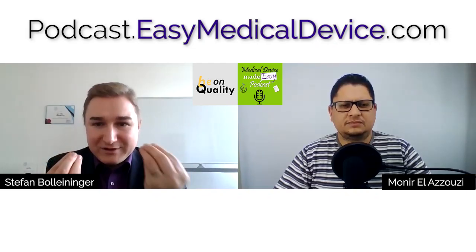However, since you can combine the audit time for ISO 13485 and for the MDR, because if MDR tells you need a notified body, it tells you in the same way, hey, you need an ISO 13485 certification. Yeah. So, or you have a type test approval or something like that. But let's go to the normal case. Normal case tells me, okay, we need a notified body. That means we need a certified quality management system. Technically, it could be 2 different companies, one a notified body, one a certification company, or it could be one company.